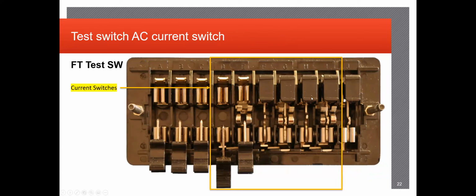Let's see. In this block right here, you can identify these as current test switches, which again, you'll have A, B, and C. But for your currents, you need an in and an out based on how current flows. It's not like a voltage where it's just measuring off a point. It has to be measured through the circuit. So you'll have an in coming in. Let's say it's coming into this D side, goes up to the relay, and then comes back out E and completes the circuit on the other side.